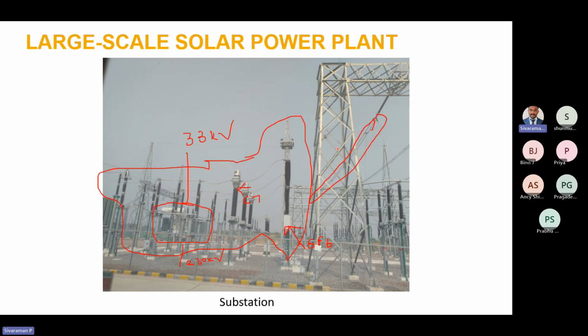Okay. In the switch gear, we will have a VCB as well as the voltage transformer PT and current transformer CT. I also explained about the bus PT and line PT. The PT installed in a bus is called bus PT, and the PT installed in the line is called line PT. Also, I gave some insight about the substation and the collector network. The medium voltage network interconnecting the inverter room to the substation is normally called the collector network. Okay.